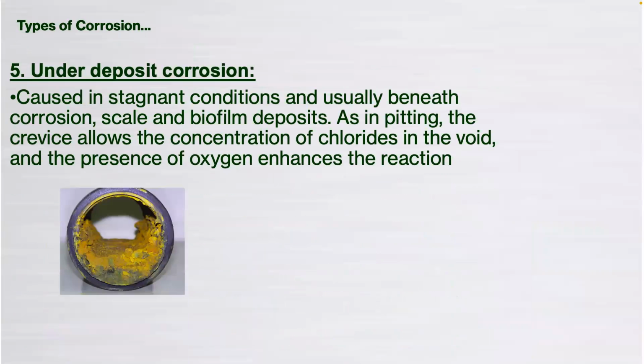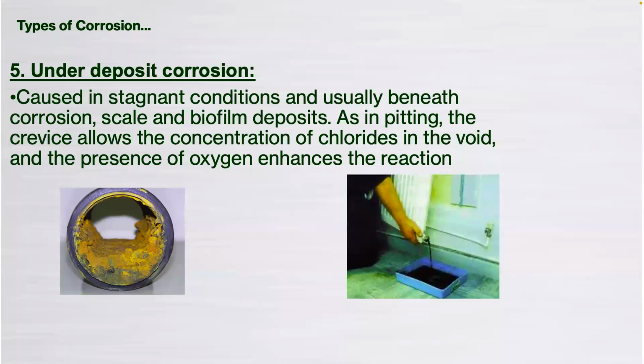Under deposit corrosion, really, as you see here, that could be a combination of corrosion, scale, or even biofilm, and it's similar to the pitting, you know, in crevice. It's really about the concentration of chlorides in the void. So what we have is where you have a high level of oxygen through the water that's passing over and a lower level of oxygen beneath, that will drive the corrosion cell essentially, and at the same time that will increase, if you like, the level of chlorides, for example, in this particular case, that could cause corrosion.